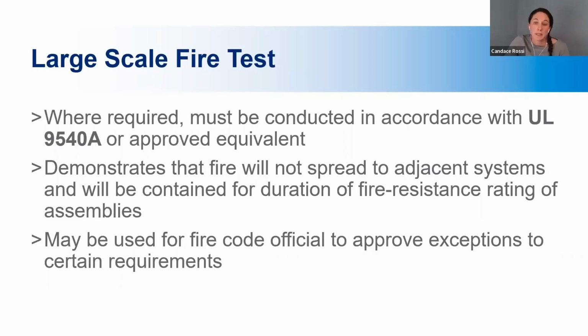The second key requirement that I want to call out is the large-scale fire test. Where required, large-scale fire testing must be conducted on a representative energy storage system in accordance with UL 9540A or an approved equivalent by an approved testing laboratory. And the test must show that a fire involving one system will not propagate to an adjacent system. It should also show that if a fire does occur, it will be contained within the area for the duration of the fire resistant rating of the room and assemblies.